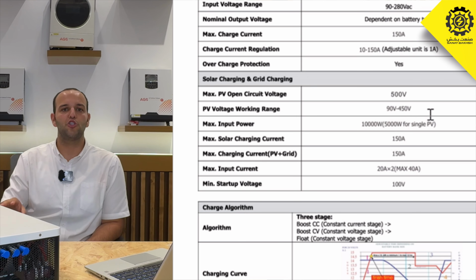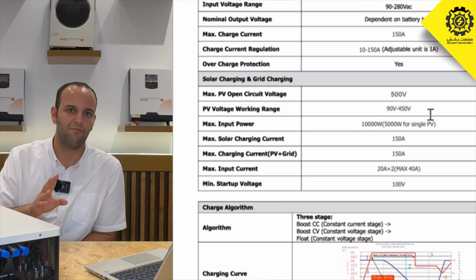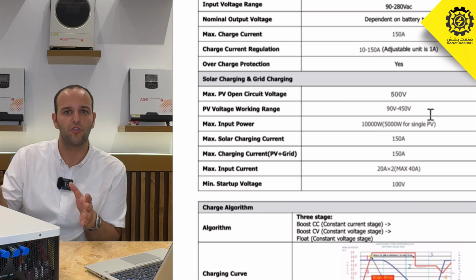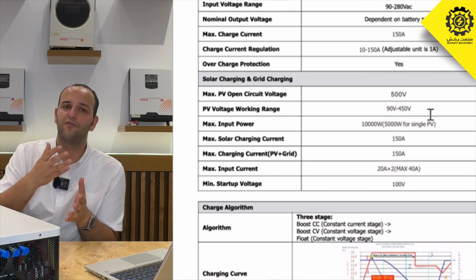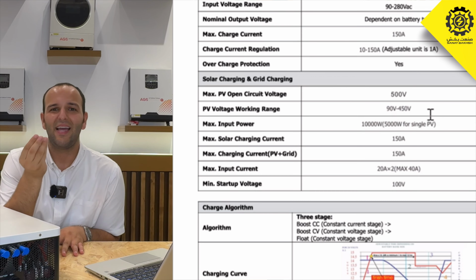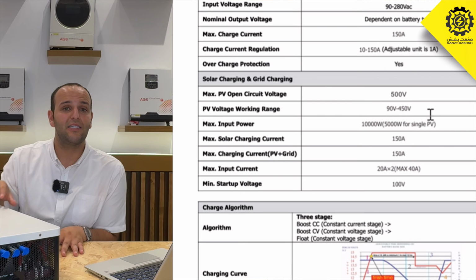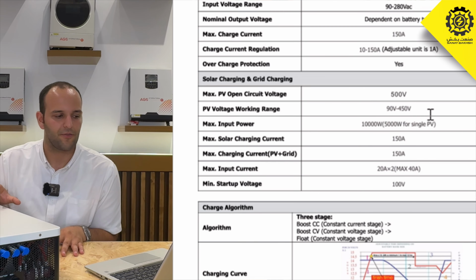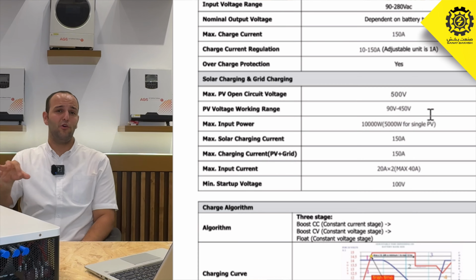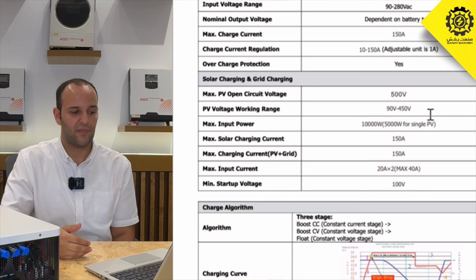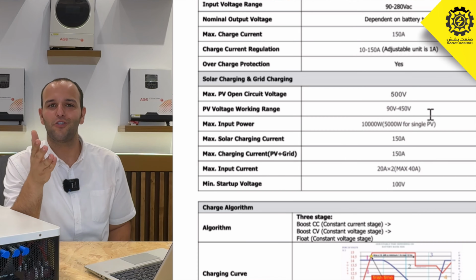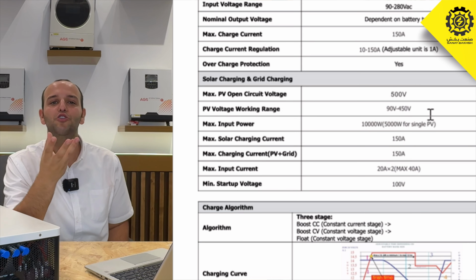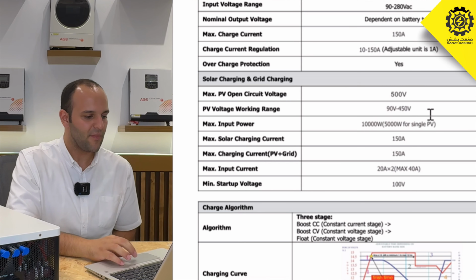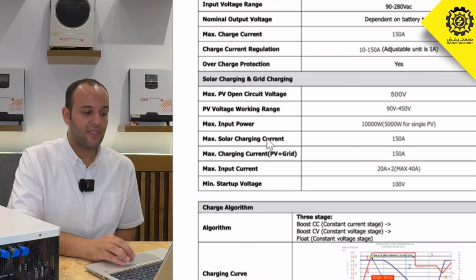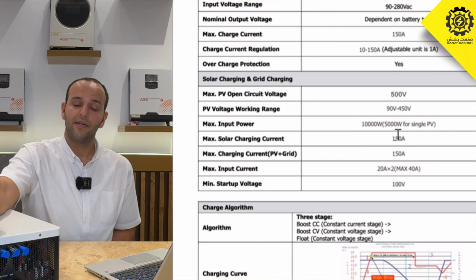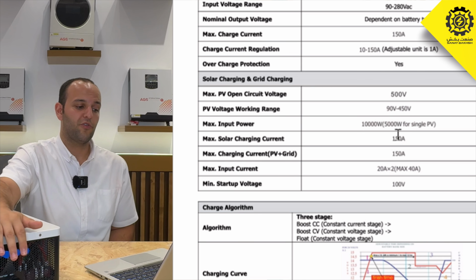This inverter doesn't support two solar panels, because two solar panels in series can only provide around 86 volts. With 86 volts, this inverter cannot turn on. You must use a minimum of 3 solar panels in series. If you connect in parallel, you just increase your current, and it's not useful for this inverter. Max input power is 10,000 watts. Each MPPT can support 5,000 watts.